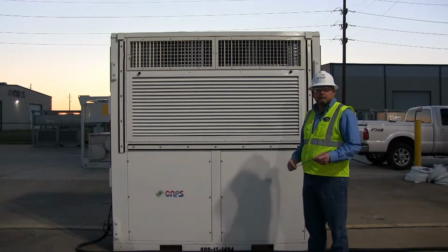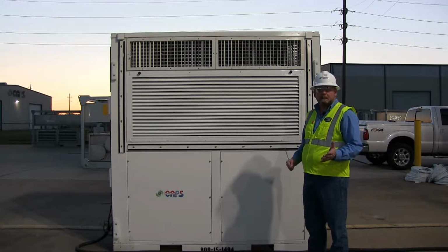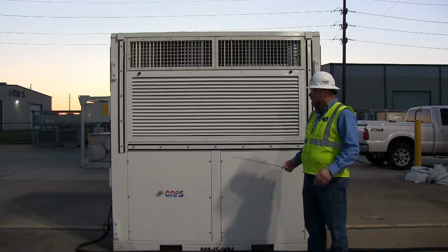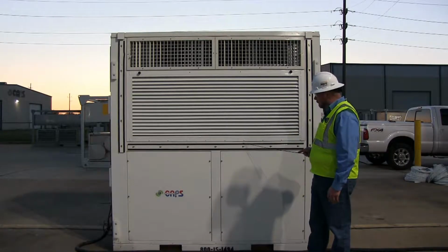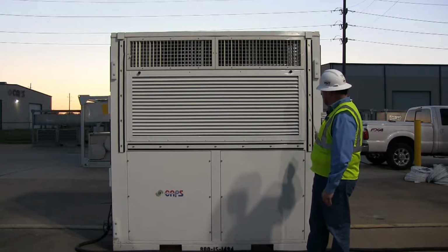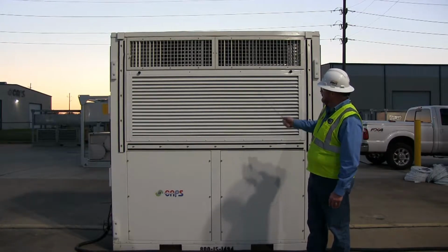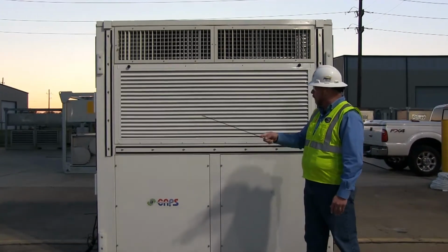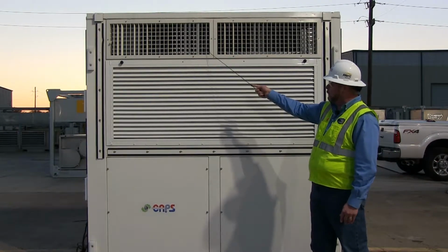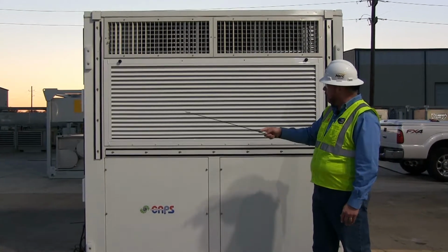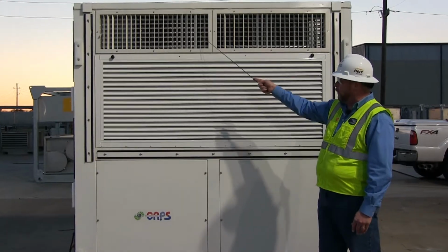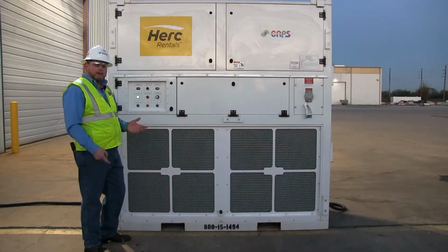The HERC 20-ton vertical event units are designed to be flush mounted to typically a fabric type tent. These bottom rails here, which go around the perimeter, this is the intake grill and this is the outlet grills here. So warm, moist air comes in, cold, dry air comes out, or cold air goes in and warm air comes out. Okay, we're complete with our setup.